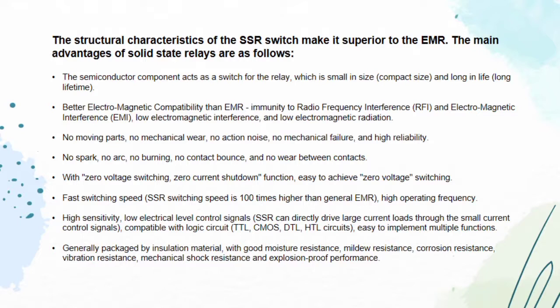Seventh is high sensitivity and low electrical level control signal. An SSR can directly drive a large current load through a small current control signal. It is compatible with logic circuits, which are TTL, CMOS, DTL, and HTL circuits, and it is easy to implement multiple functions. And lastly, it is generally packaged with insulation material with good moisture resistance, mildew resistance, corrosion resistance, vibration resistance, mechanical shock resistance, and explosion proof performance. So these are the main advantages of solid state relays.